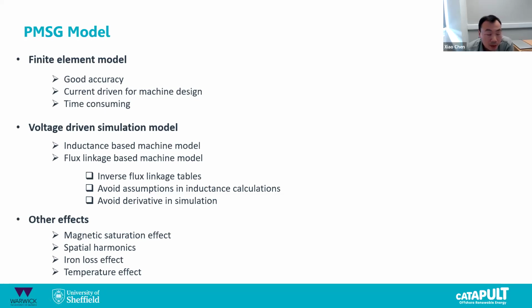In terms of the permanent magnet synchronous generator model, typically we talk about two models. One is the finite element model. This type of model has very good accuracy, but it is mainly for machine design with current-driven sources, because if you use it directly for simulation, it will be very time consuming. When we talk about simulation, a more popular model is the voltage-driven simulation model. Typically we have the inductance-based machine model, and we also have another type, the flux linkage-based machine model.